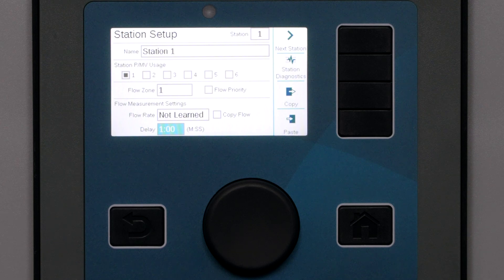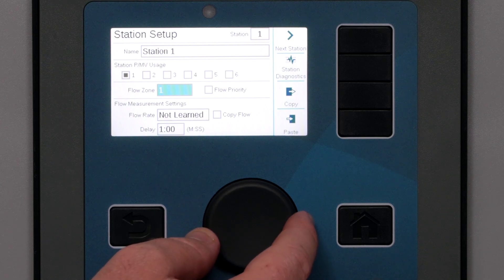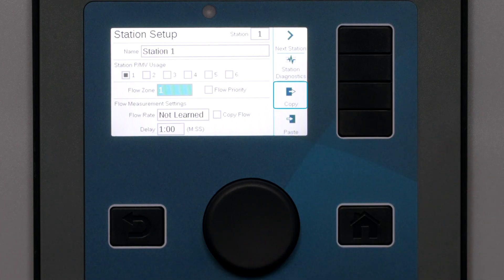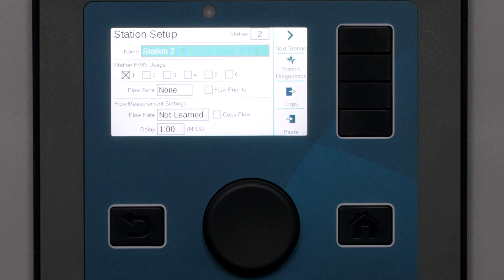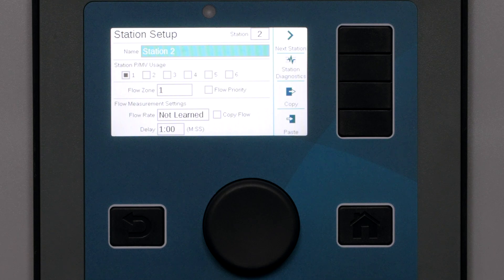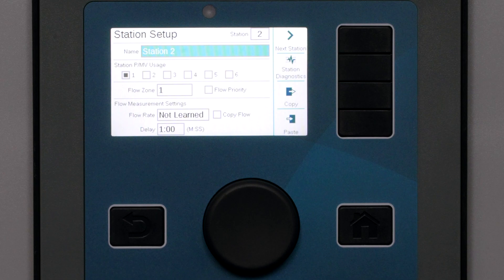With the first station attached to flow zone 1, click the copy key. Then use the next station key to advance to the next station number in the flow zone and click the paste key. This will quickly attach the new station to flow zone 1. You can click next and then paste to advance quickly through a large list of stations. When you believe the flow zone setup is complete, there is a quick way to review it — go to the Flow menu and select the Hydraulic Summary.